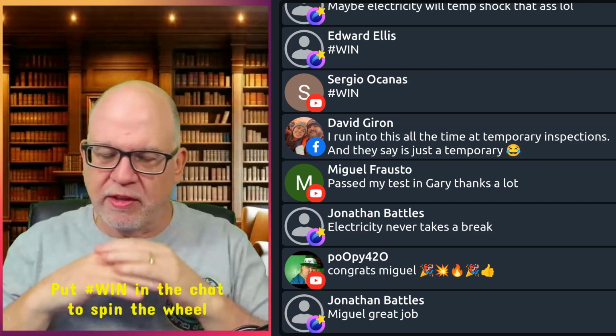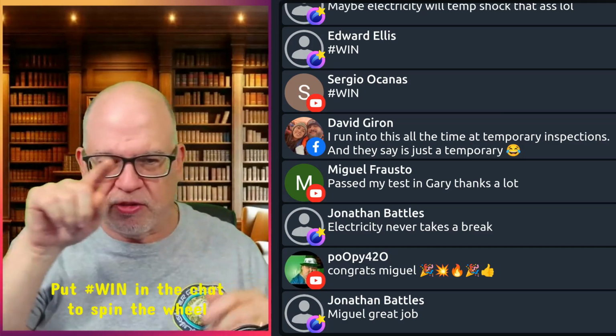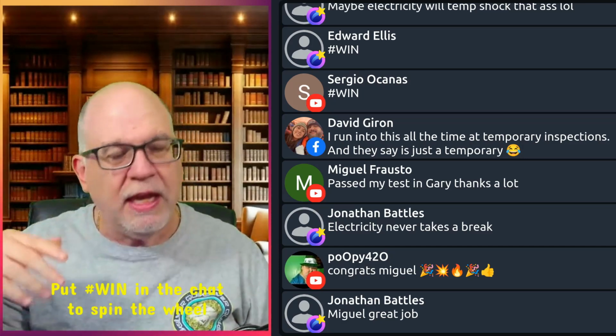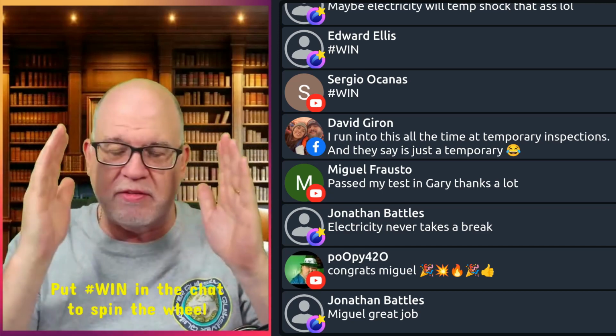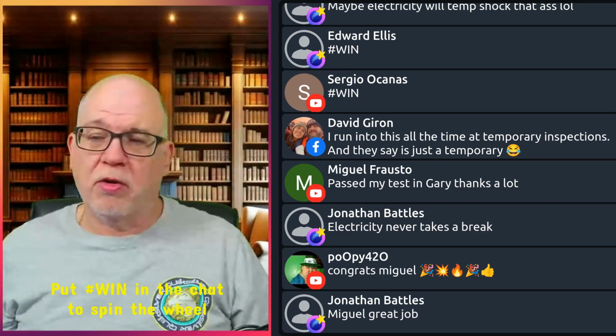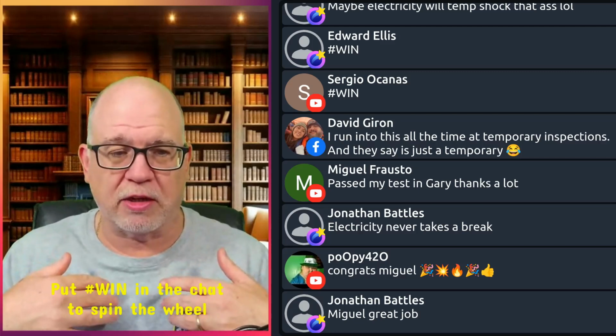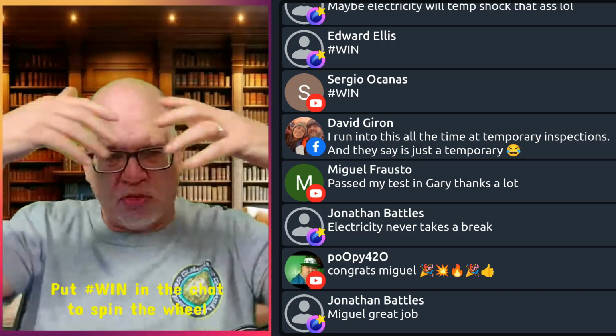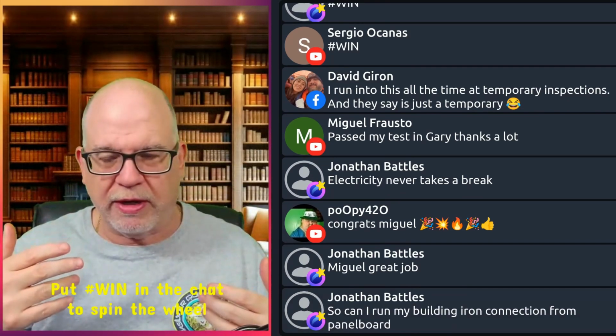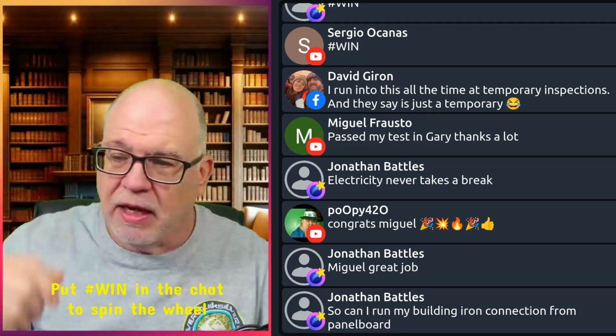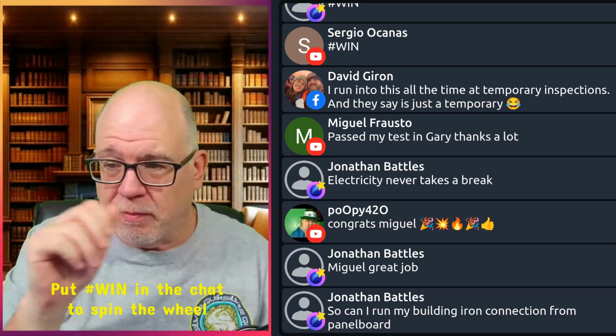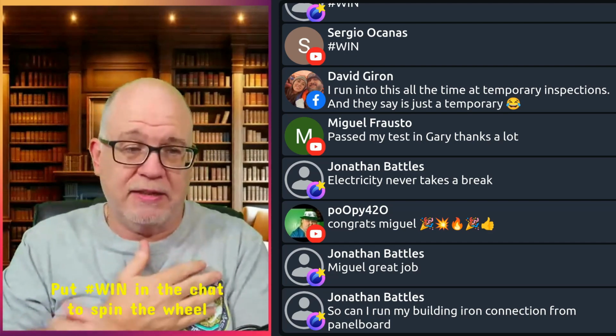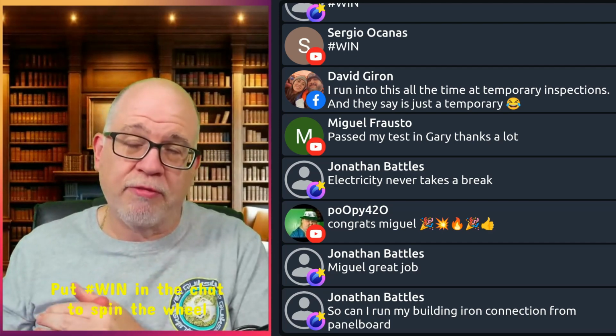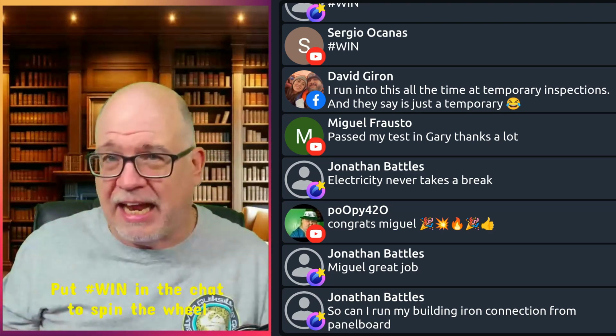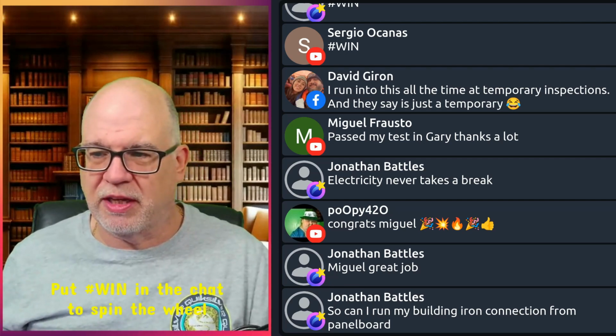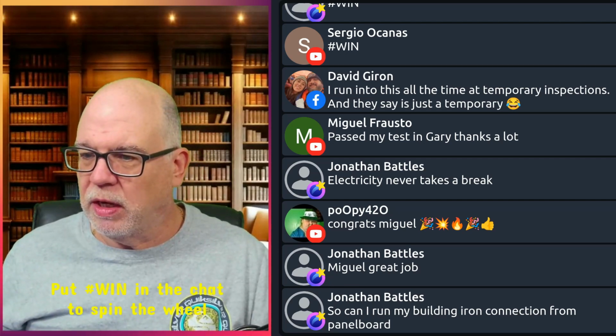Doesn't matter. If you see the verbiage in it and you can read it and it has it in both directions, this way, or if you flipped it, you can read it this way, then typically that's going to be, doesn't matter. And it's very common to turn a panel so that the breaker's closer to reduce the length of the conductors, okay? And having to run conductors through the enclosure all the way up to the top of the breaker. Now, if it allows you to do that, if it is a horizontal mounted circuit breaker, then it is fine, okay? But if it is on, off marked, and it is being installed vertically, it has to be on in the up position in accordance with 240.81, I believe.